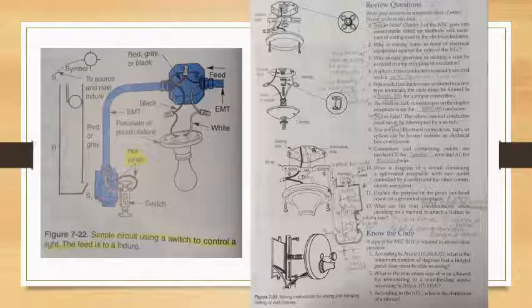And the know the code portion of these questions. Number 1. According to article 110.26A2, what is the minimum number of degrees that a hinged panel door must be able to swing? And if you find on the 2017 NEC page 70-47, it would be 90 degrees. Question 2. What is the maximum size of wire allowed for terminating to a wire binding screw according to article 110.14 of the NEC? That is article 110.14A. And according to the NEC 2017, page 70-45, that is 10 AWG maximum size for the allowed wire for terminating to a wire binding screw.